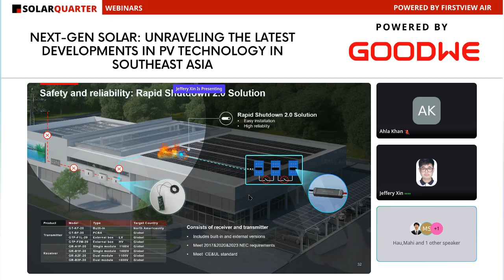And the SPD protection on the DC and AC side - by default GoodWe inverters can meet the Type 2 SPD level, and if some areas have special needs for Type 3, we can meet them.